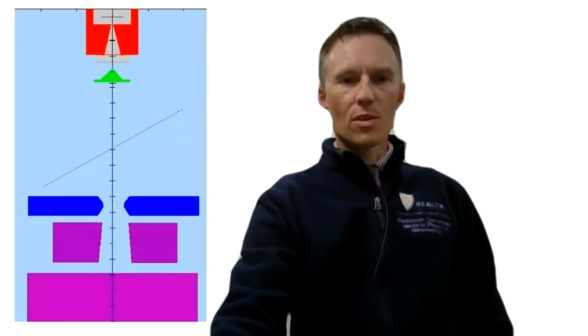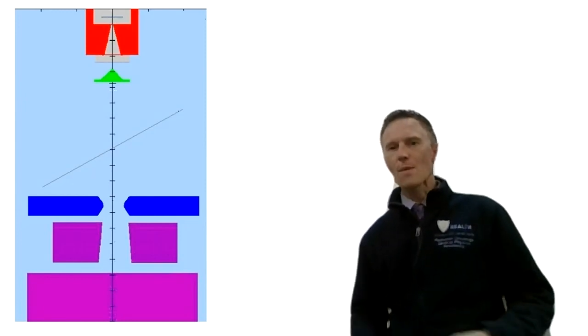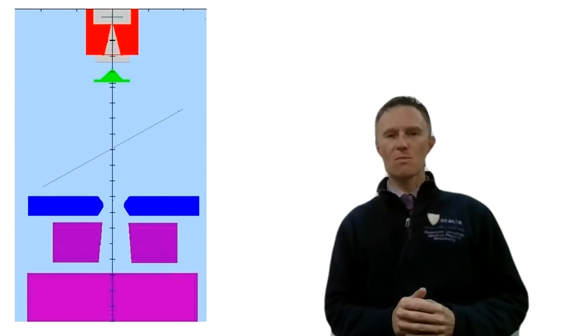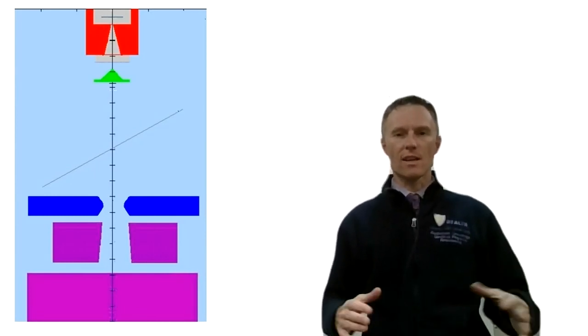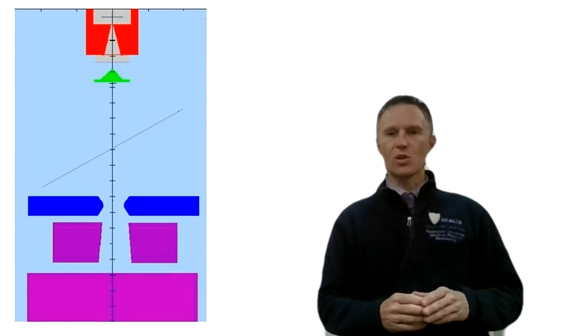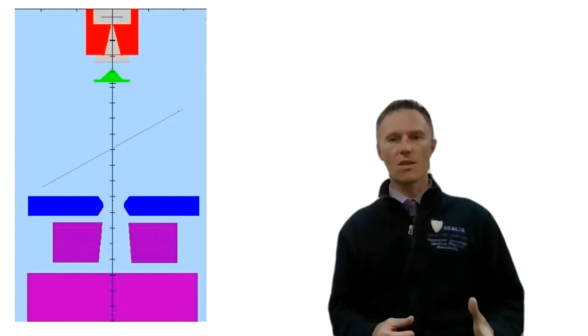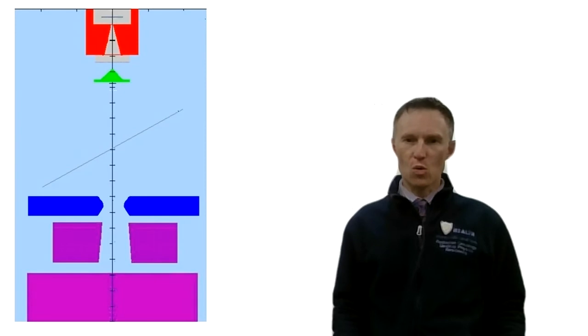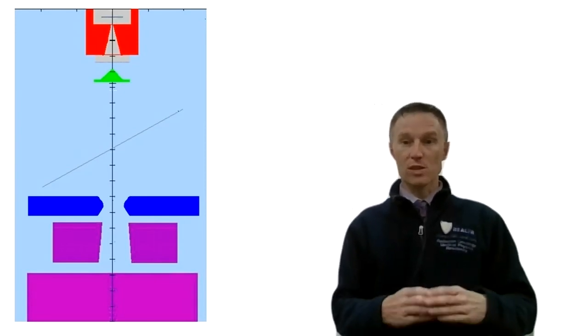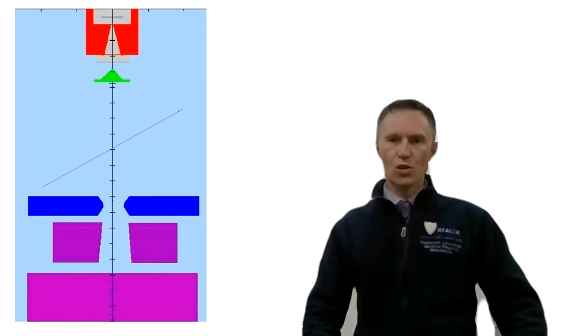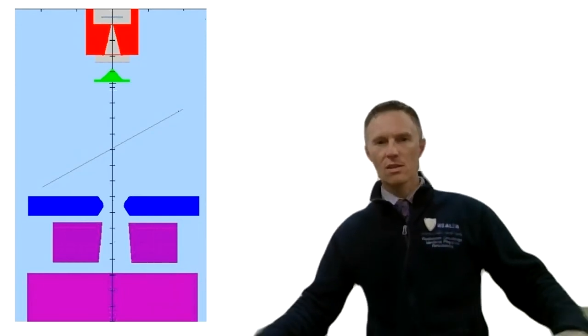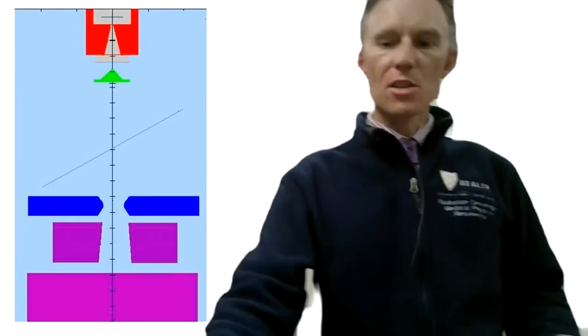Let's start with a quick, very simple schematic of what these components look like. At the very top of this image in red is the primary collimator. The primary collimator is essentially just a conical hole that produces a beam of circular cross-section. As electrons strike the target and produce a beam of photons, the cross-section will be circular. The beam diverges downwards, and the primary collimator is used to prevent it from spilling out over the sides of the jaws.